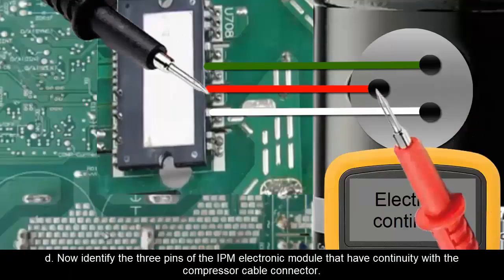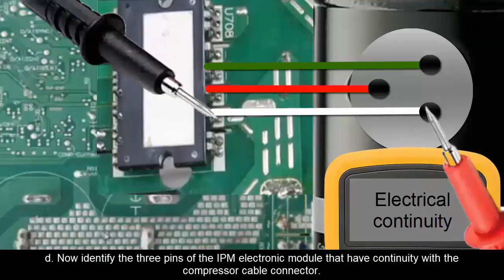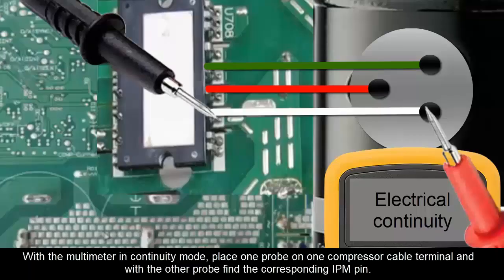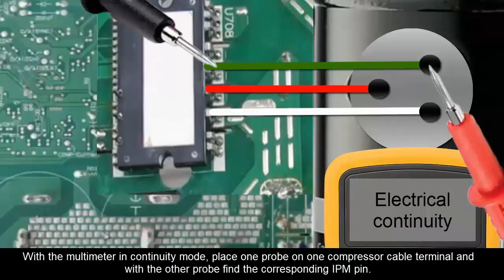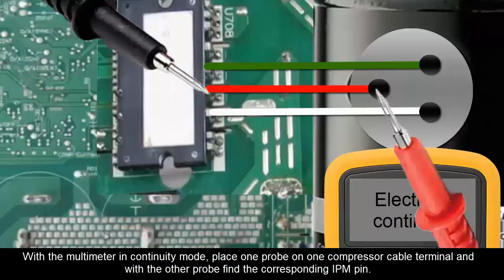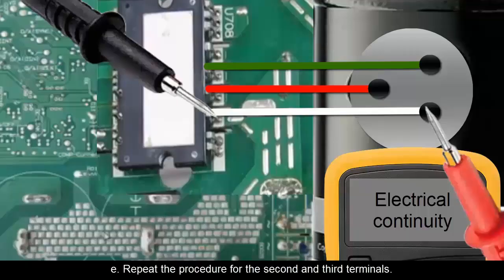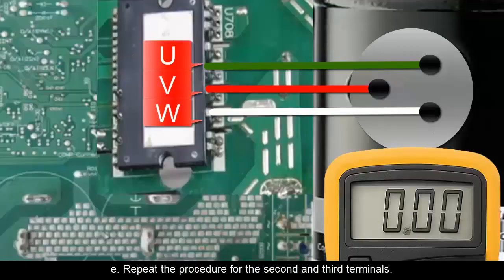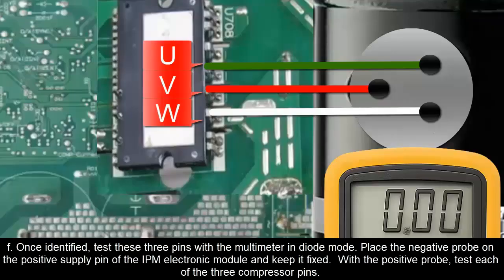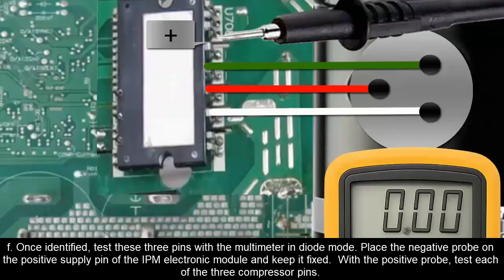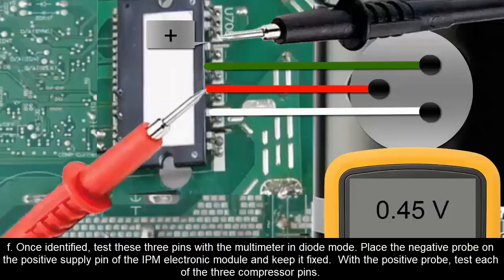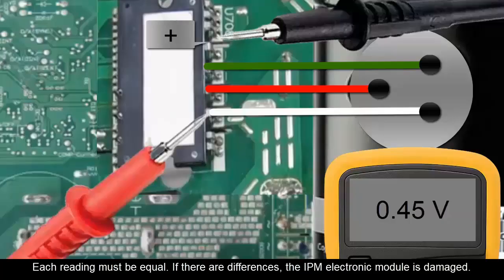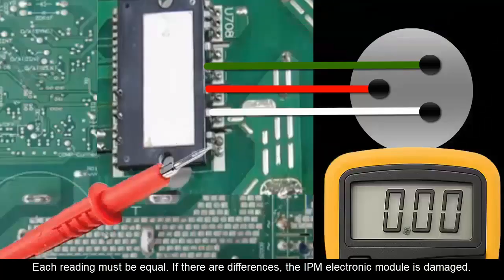D. Now identify the 3 pins of the IPM electronic module that have continuity with the compressor cable connector. With the multimeter in continuity mode, place one probe on one compressor cable terminal, and with the other probe find the corresponding IPM pin. E. Repeat the procedure for the second and third terminals. F. Once identified, test these 3 pins with the multimeter in diode mode. Place the negative probe on the positive supply pin of the IPM electronic module and keep it fixed. With the positive probe, test each of the 3 compressor pins. Each reading must be equal. If there are differences, the IPM electronic module is damaged.